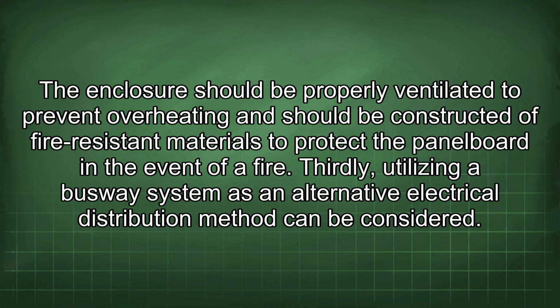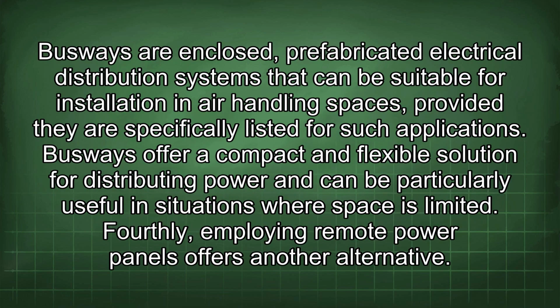Thirdly, utilizing a busway system as an alternative electrical distribution method can be considered. Busways are enclosed, prefabricated electrical distribution systems that can be suitable for installation in air handling spaces, provided they are specifically listed for such applications. Busways offer a compact and flexible solution for distributing power and can be particularly useful in situations where space is limited.